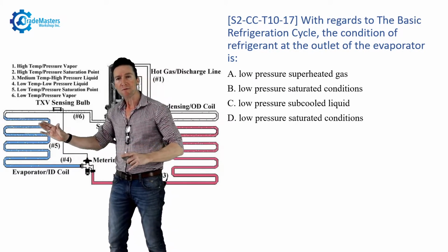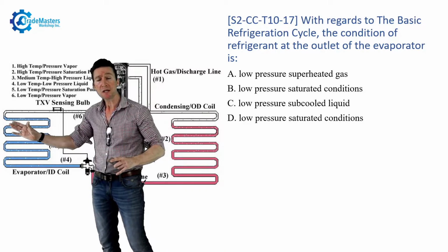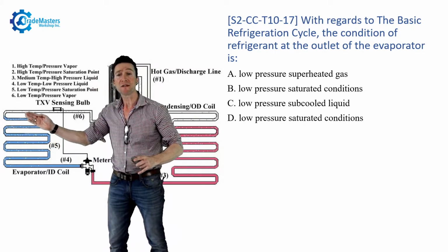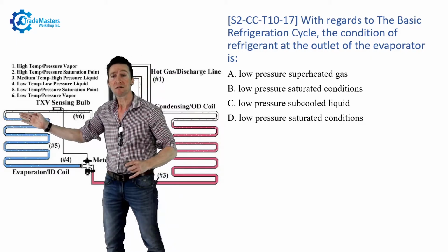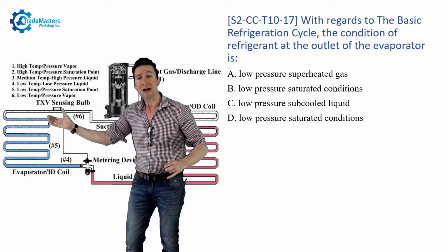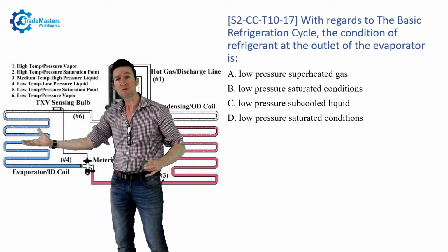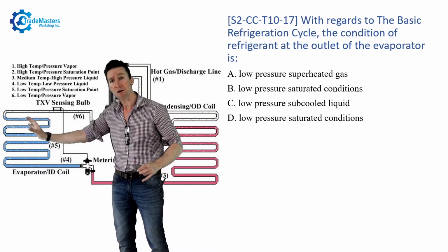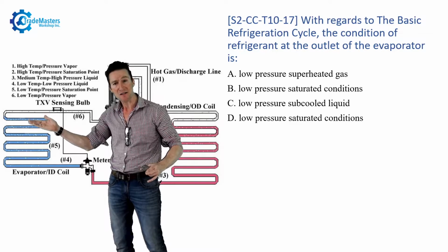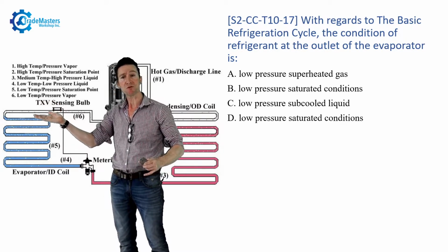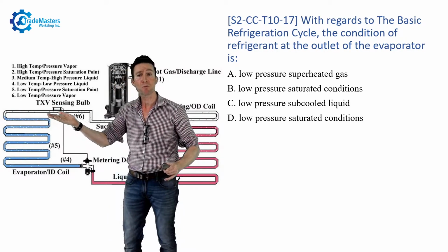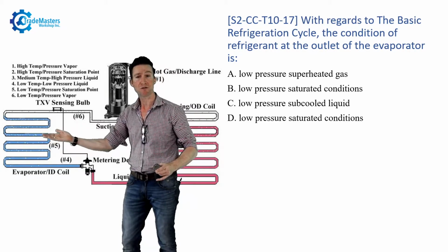Therefore, when the refrigerant leaves the evaporator, it should be a 100% vapor state. But because it's still colder than the air blowing over the evaporator here in the last few passes, that 100% vapor will continue to absorb some heat energy from the air blowing across the coil. It causes an increase in sensible temperature of the gas and therefore superheats it above its evaporation temperature.